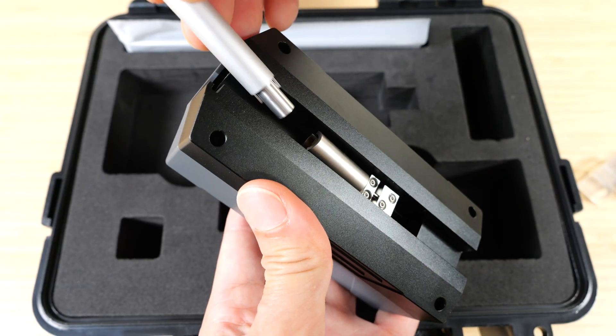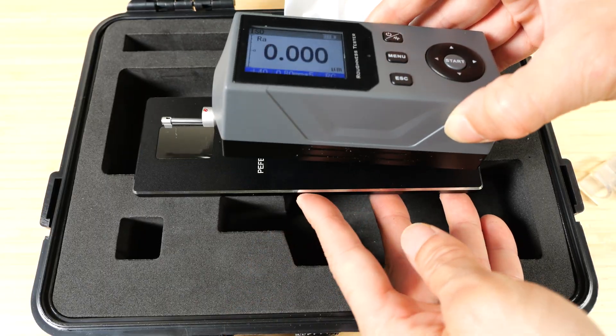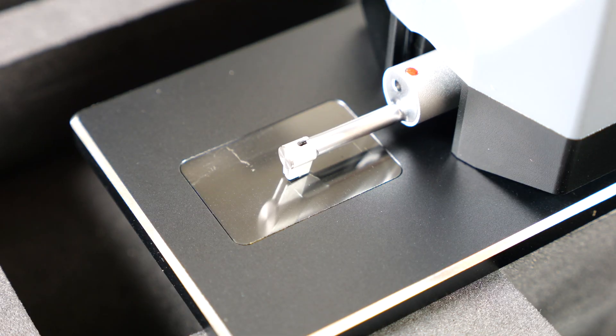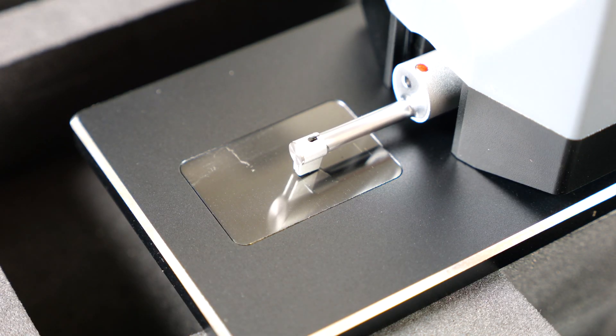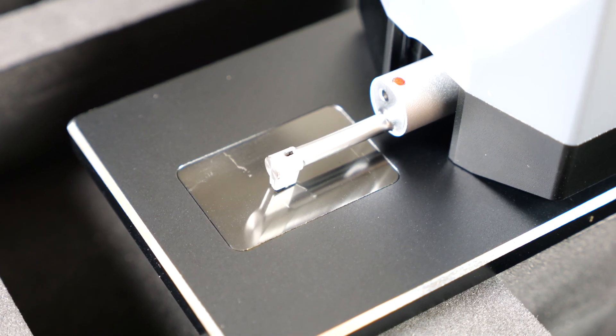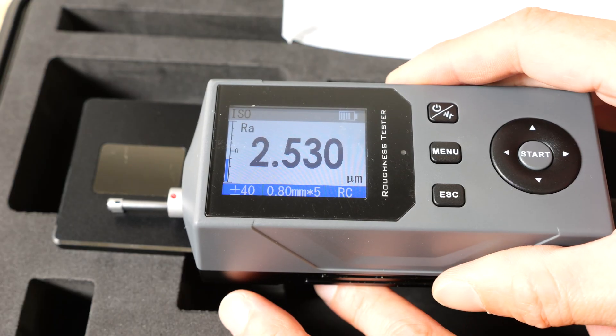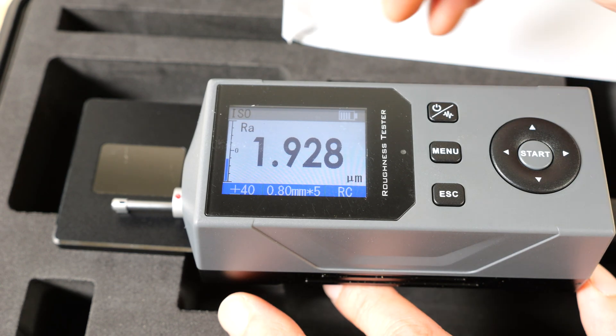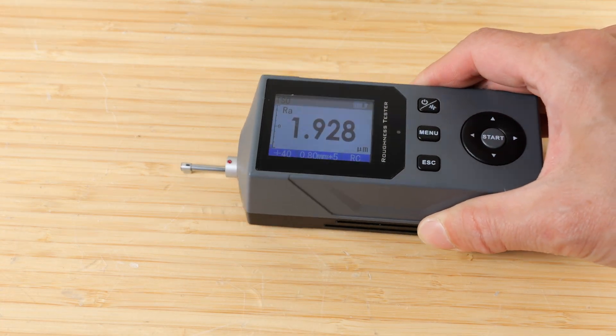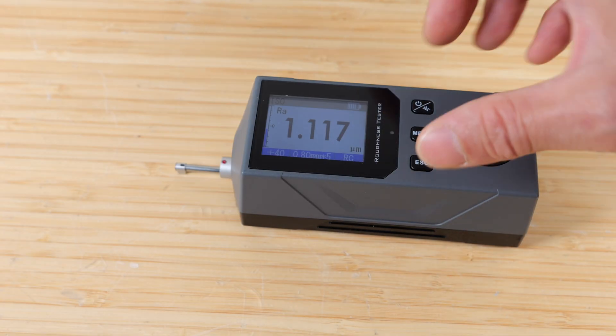Attach the sensor to the main body and press and hold the power button to turn it on. I'll use the reference standard plate — put this right on top and press start to do the measurement. 2.530 microns. I'm going to move this over a little bit and measure that. 1.928. So I think I can measure this desk right here — the wood pattern. 1.117.